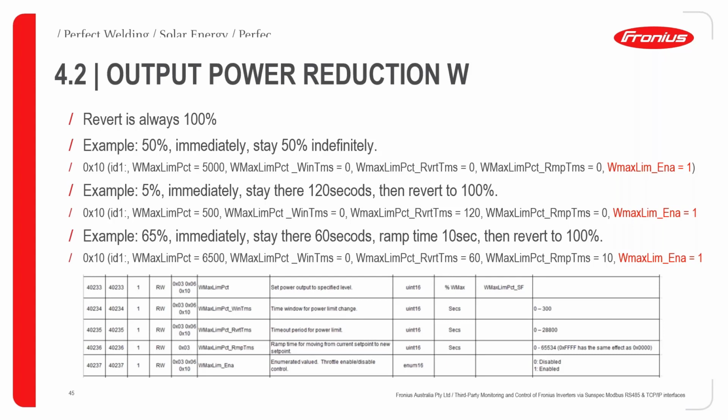And the default, if you don't engage the mode or the mode lapses, it will always be 100% of the system power, of the inverter power. Remember, we say 100%, this is 100% of the inverter power itself. So if it's a 25 kilowatt, we mean 25 kilowatt. Whether actually 25 kilowatts is going to come depends on the input. We always want to give 100%. This is how the mode works and how SunSpec defines it.